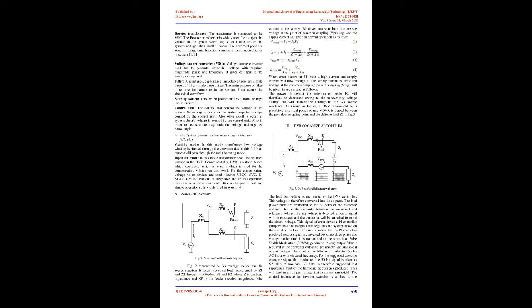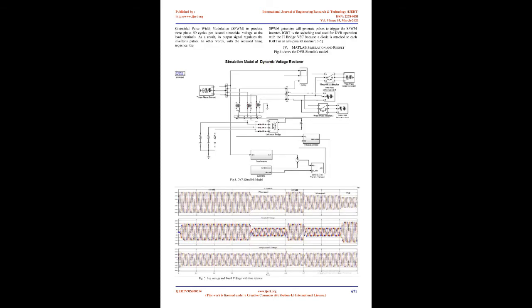The system operates in two main modes, which are the following. Standby mode. In this mode the transformer low voltage winding is shorted through the converter. Due to this, full load current will pass through the main circuit. Injection mode. In this mode the transformer boosts the required voltage in the DVR.